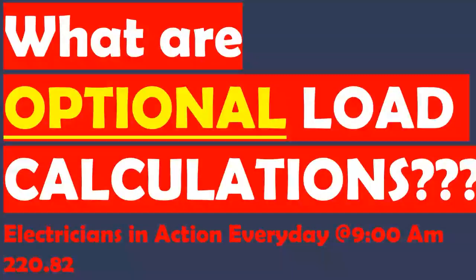Out in the field, you may be tempted to use the optional method for a load calculation. Off the cuff, you could probably use it and end up pretty accurately with your load calculations. But if any inspector asks you to do a load calculation, just go ahead and do the standard method. They're not going to want to see the optional method because it's likely going to give you a smaller amp draw, which allows you to have things in your favor as far as sizing pipe, wire, and the service.